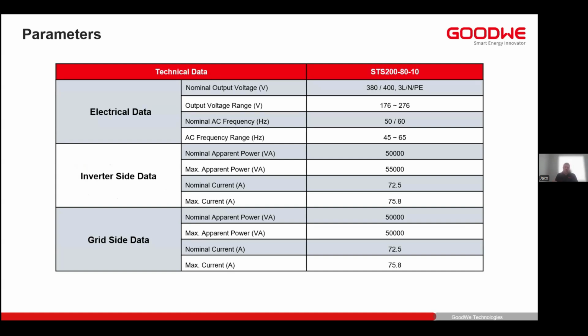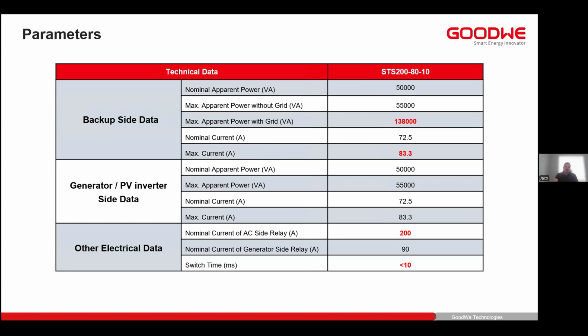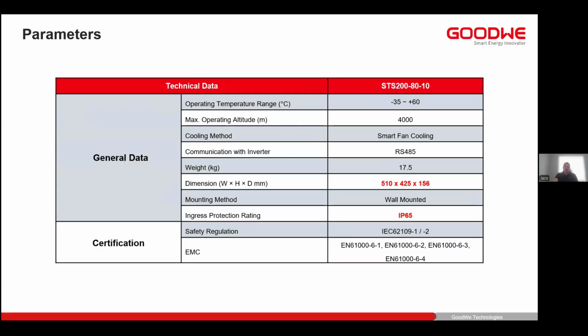Output voltage range is from 176 to 276 volts. And as I mentioned, on the grid side, it will allow a maximum of 55 kilowatt constant output. And then on the output backup side, 138 kilowatt of pass-through capability. Right, as I mentioned, the unit is outdoor rated, so IP65 rated, and only 17.5 kilograms. All the necessary certifications have been done, and we have just about 70 sites where we've already deployed this solution.